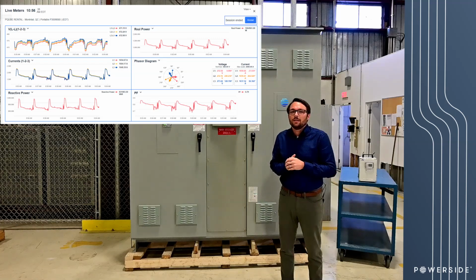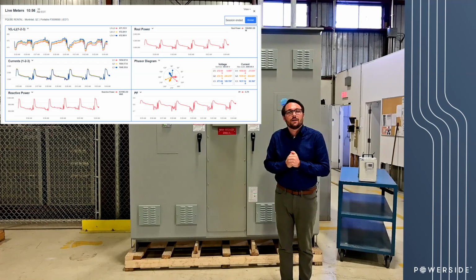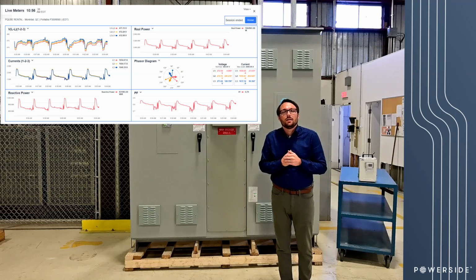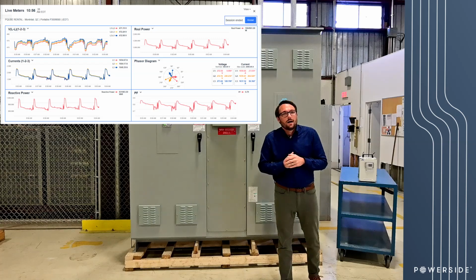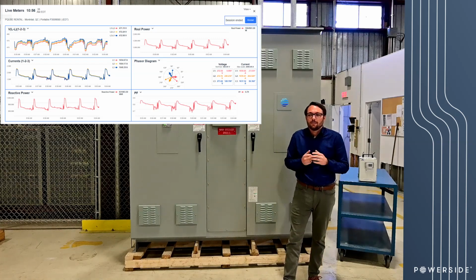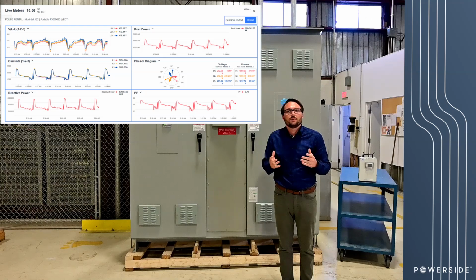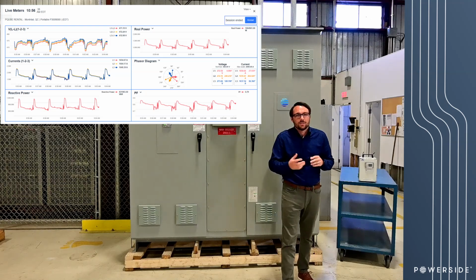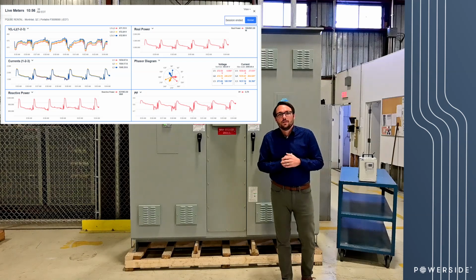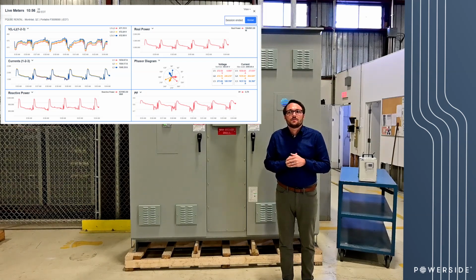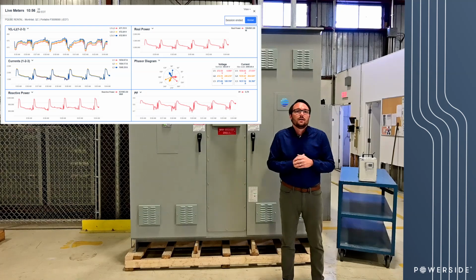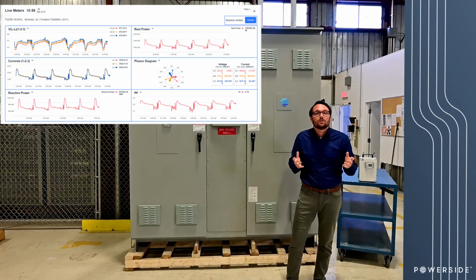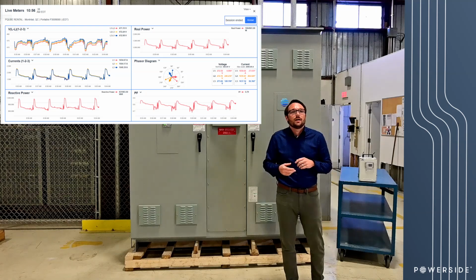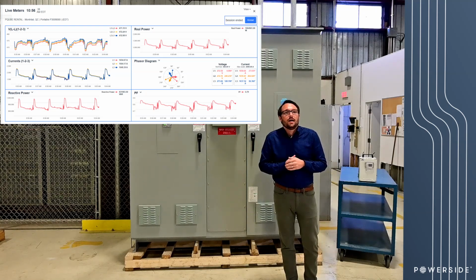Now, what you're seeing on the image is a function from our live meters capability in our CubeScan platform. And you can set these parameters to look at anything, but it's very helpful in understanding what's happening in real time. And so as you can see here, the operation for this pressing cycle happens roughly every 1 to 2 minutes. You get certainly a peak in current, the voltage drops, you have increase in kVAR, and the power factor, of course, that you need to correct for.